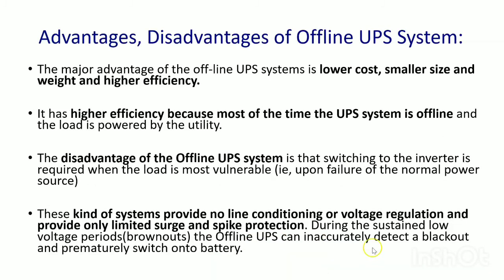The major advantages of offline UPS are low cost, small size and weight, and higher efficiency. Online UPS systems are complex, heavy, and high-cost, whereas offline UPS is simpler and lower cost. It has higher efficiency because most of the time the UPS is in offline mode and the device gets power directly from the mains during normal operation.